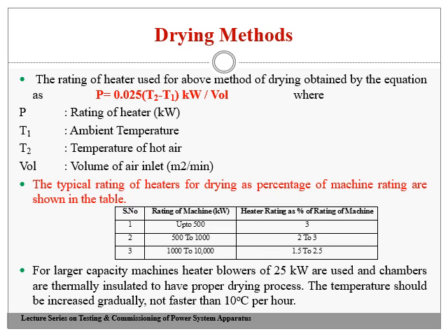In similar fashion, when the capacity increases, the percentage of the rating of the heater required goes to 2 to 3% of maybe 1000 or maybe 500. Likewise, if the machine rating is 1000 to 10,000, at that time I may require a resistor heater capacity of around 1.5 to 2.5 depending upon the capacity. For the larger capacity machines, heater blowers of 25 kilowatt are used. As the capacity increases, this percentage may not work out. Heater blowers of 25 kilowatt are used for larger capacity induction motors, otherwise as specified by the standard specifications.